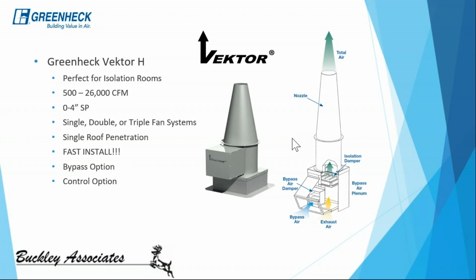The fan that you see here on the left is our standard version of this fan. This is an exhaust only configuration. However, these fans do have the option to add a bypass to maintain constant speed and assist with dilution of air as these hazardous chemicals are exhausted. The nice thing about this specific Vektor H, and probably why we see it used the most, is it's a quick and easy install. All you have to do is drop this fan on the roof. It's got a single penetration that's required, and run power to it, and you're good to go. This is probably the most common fan we're seeing used for these isolation room applications.